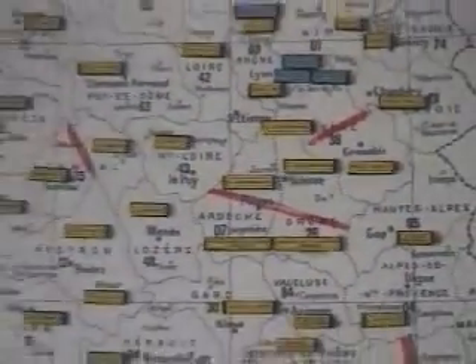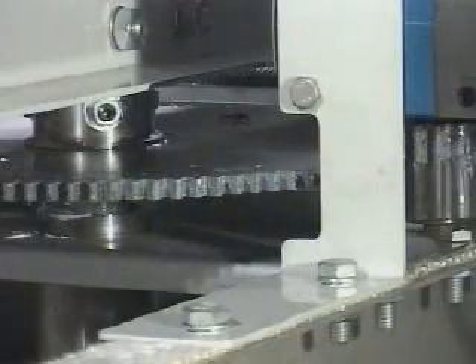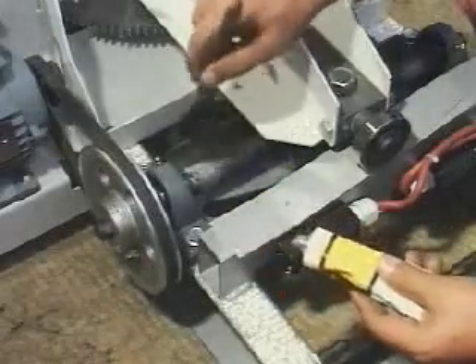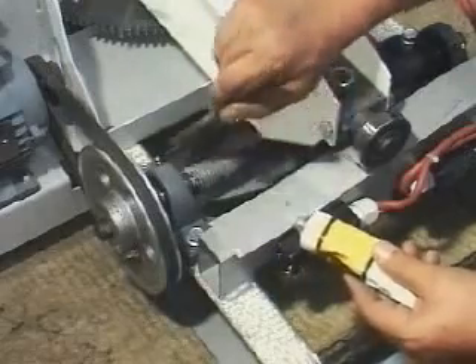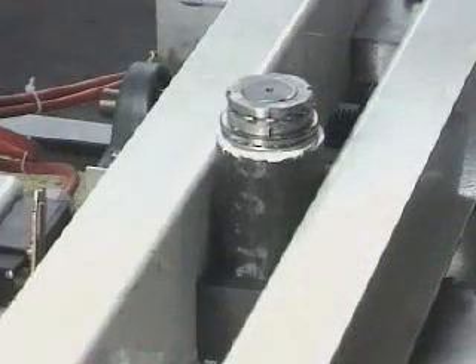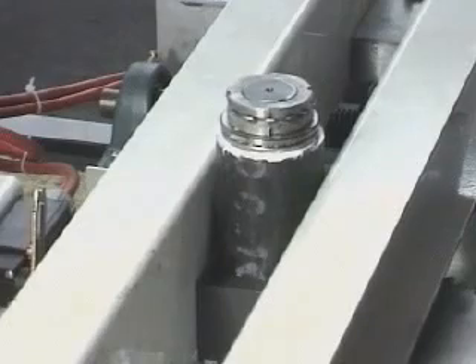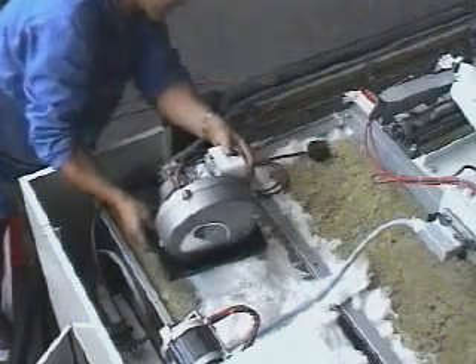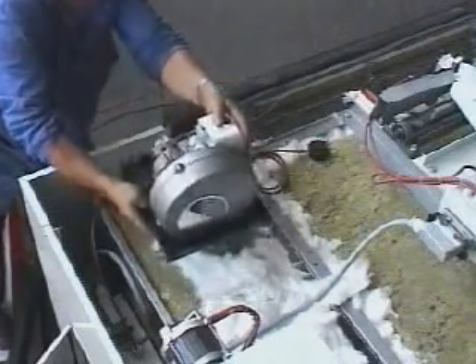Product reliability depends on correct maintenance by the customer and regular technical servicing by the distributor or agent, for example through a maintenance contract. Take particular care to grease moving parts. The gears, the endless screw disc lifter, the thrust bearing and bronze bushes on the drive shaft. Do not forget to inspect and test the burner every year.